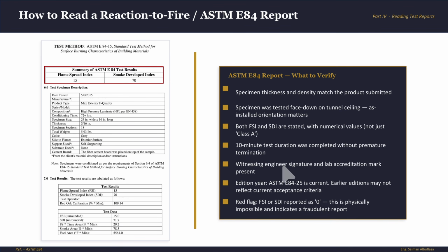And then the witness engineer signature and accreditation mark, both must be present. No signature, not a valid report. And then the edition year. For example, if 2025 is the newest edition, then the test must be done to the current edition. And if FSI or SDI is reported as 0, this is physically impossible. Any organic material, wood composite, rubber, textile, will always produce a measurable flame spread in the Steiner tunnel test. A result of 0 is physically or scientifically impossible.